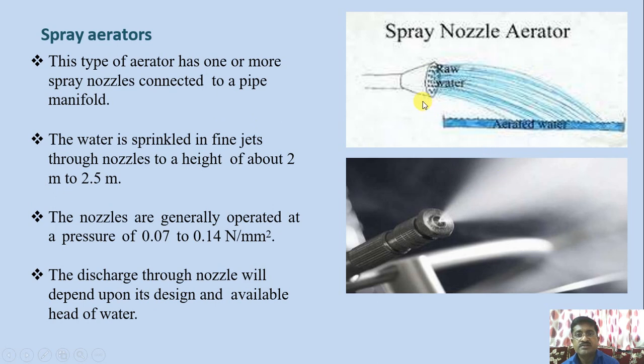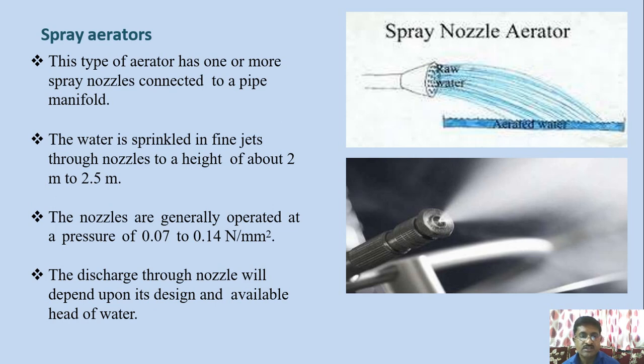Spray aerators use one or more spray nozzles connected to a pipe manifold. The water is sprinkled in fine jets through nozzles to a height of 2 to 2.5 meters. The nozzles are generally operated at a pressure of 0.07 to 0.14 Newton per mm squared. The discharge through the nozzle depends upon its design and available head of water.